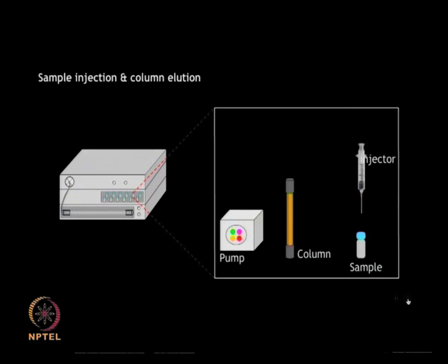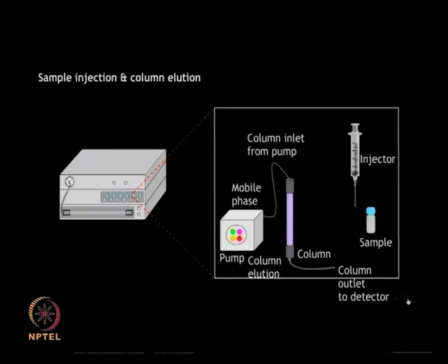The sample injector system may be automatic or manual. The automatic sample injector uses a syringe to inject the sample, which is placed in a vial, directly into the column. Once the sample is injected, mobile phase flows into the column through the pump. The column consists of a stationary matrix that preferentially binds certain analytes. The outlet from the column enters the flow cell, where it can be detected.